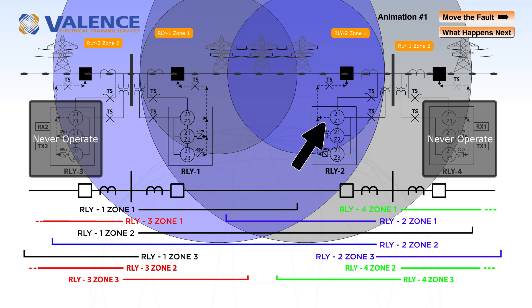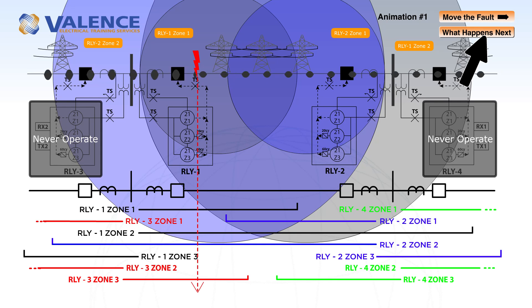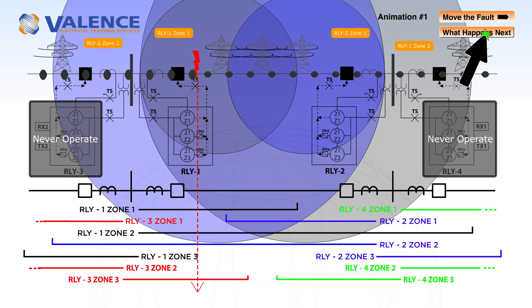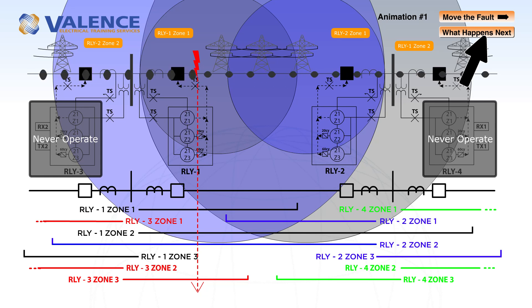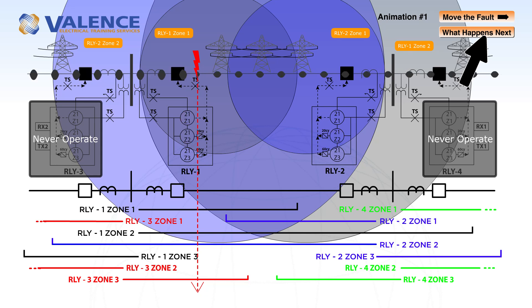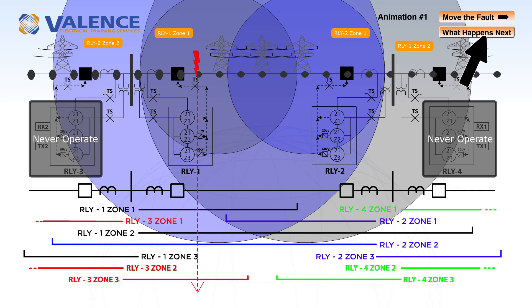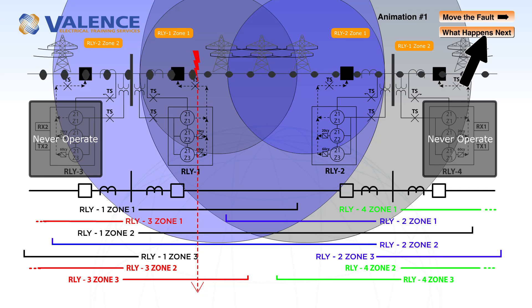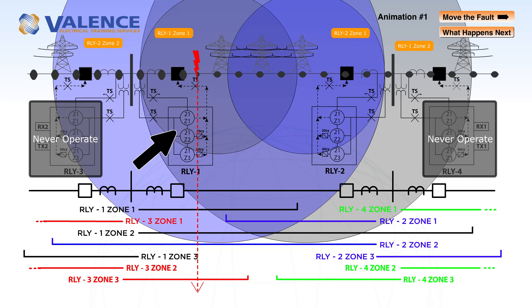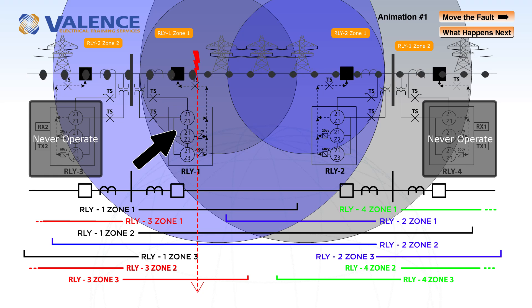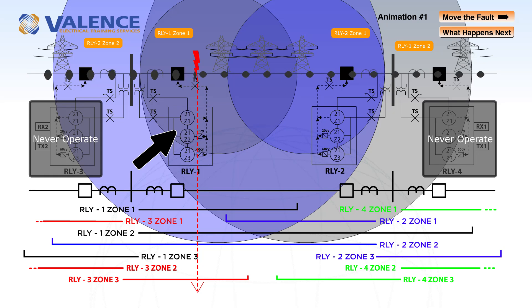If we simulate a fault very close to relay 1, zone 1 and zone 2 will both pick up. This is one thing that you really have to think about when you are doing end-to-end testing. We often think in terms of what trips a relay, but communication assisted tripping schemes share information when elements pick up, not when they trip. Both zones are going to pick up if the fault is closer to one side.